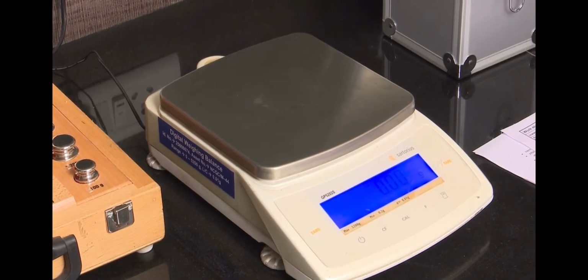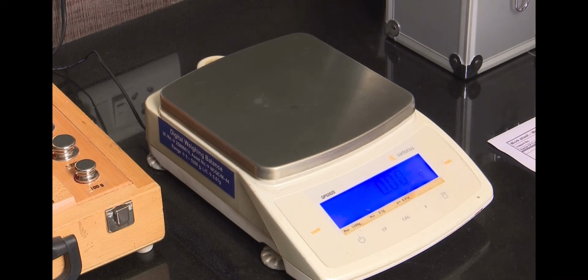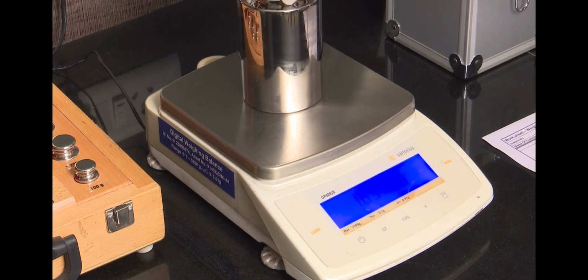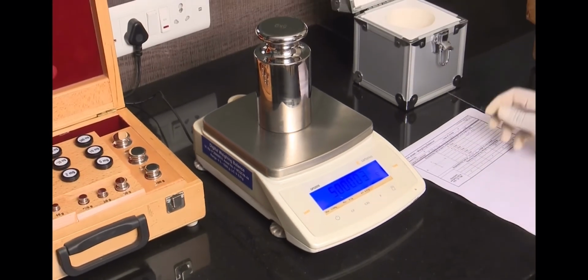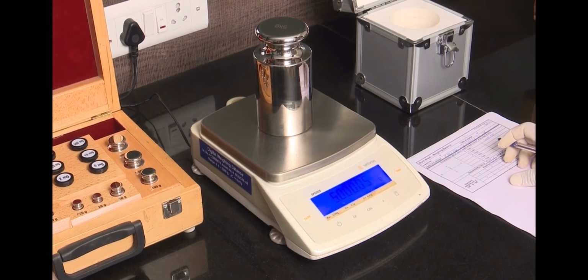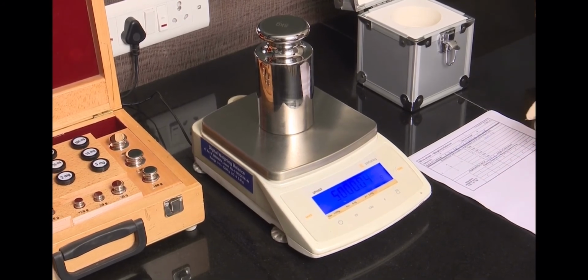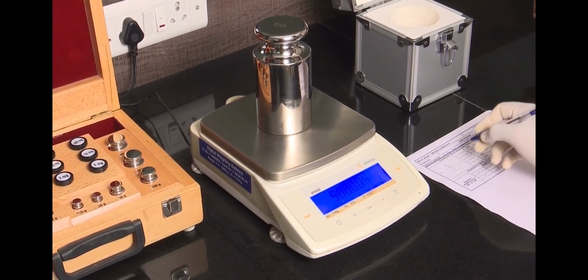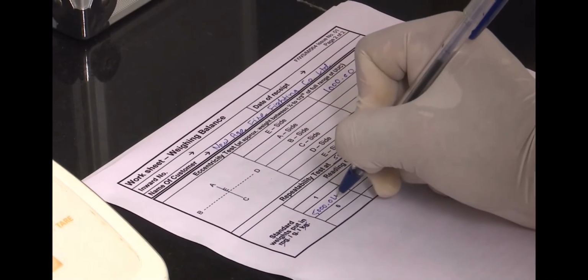Now I am performing repeatability test. Select reference standard weight nearer to the full span of the weighing balance under calibration. In our case, I have selected 5000 gram. Press tare button to make the reading 0. Now take 5000 gram reference weight and put it on the center of the pan of balance. Wait and allow it to stabilize. Note down the reading shown by the balance for reference standard weight put on the center of the pan of the balance.